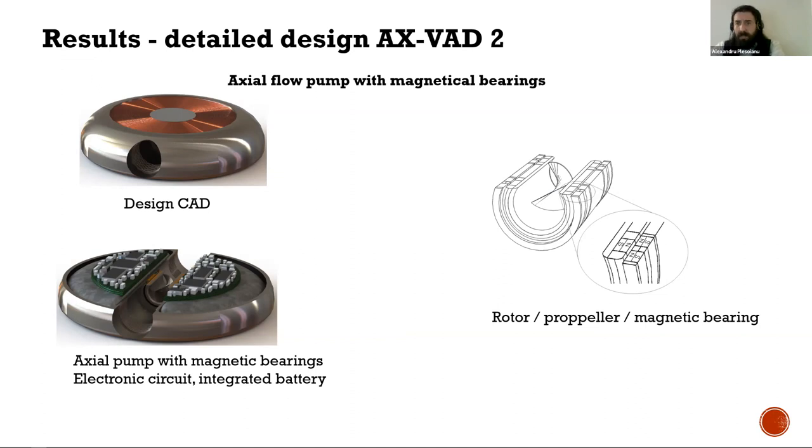The electronic system contains a power management block, a microcontroller, a motor driver, and a communication block. The energy wirelessly transmitted from an external source is received through the antenna and distributed to the power management block, for both device operation and battery charging. The battery is used as the internal power source when the external source is interrupted.